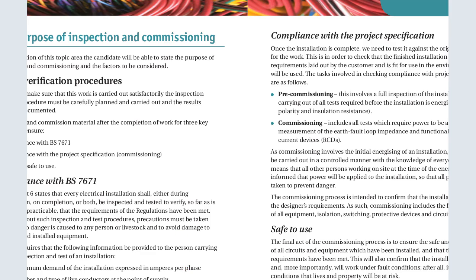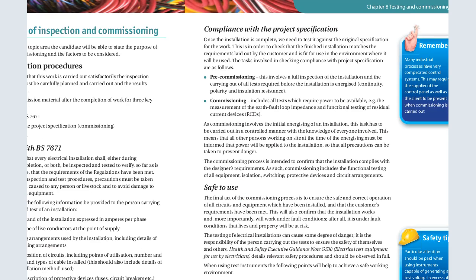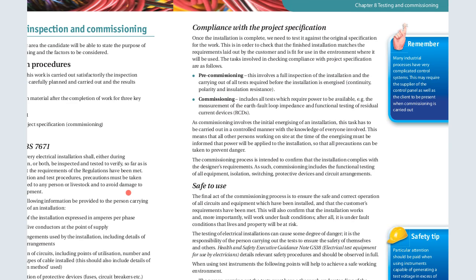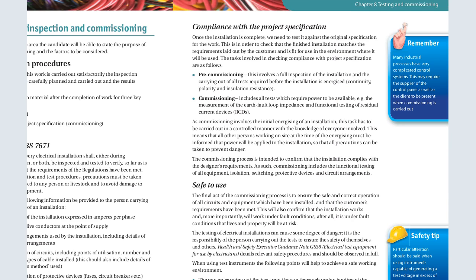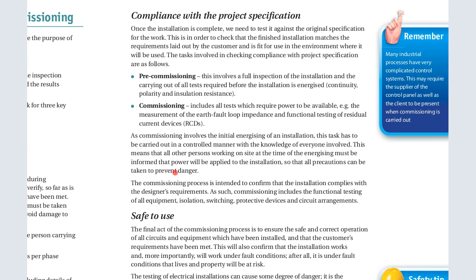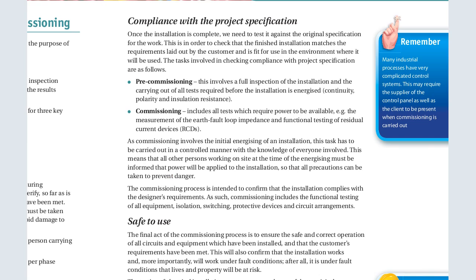The next thing is compliance with the project specification. Once the installation is complete, we need to test it against the original specification for the work. This is in order to check that the finished installation matches the requirements laid out by the consumer and is fit for use in its environment. The following tasks have to be carried out to ensure compliance. That is pre-commissioning, which involves the full inspection of the installation and carrying out all tests required before the installation is energized.